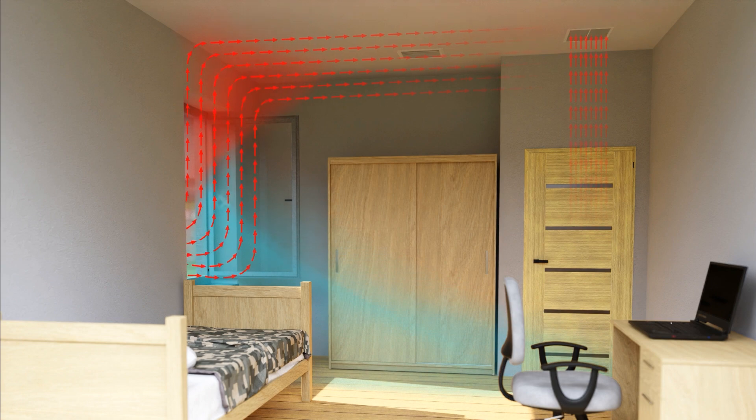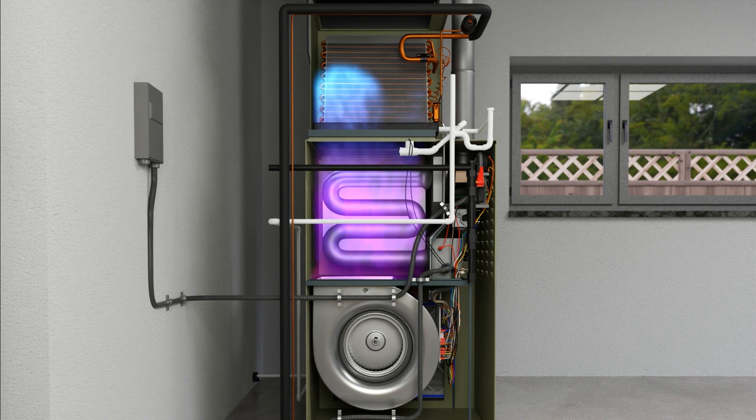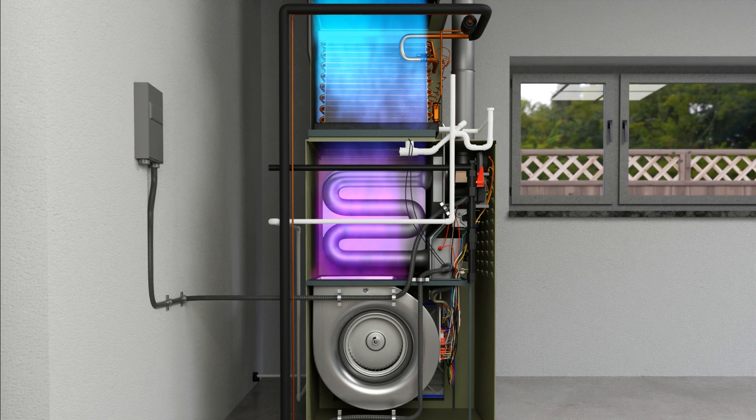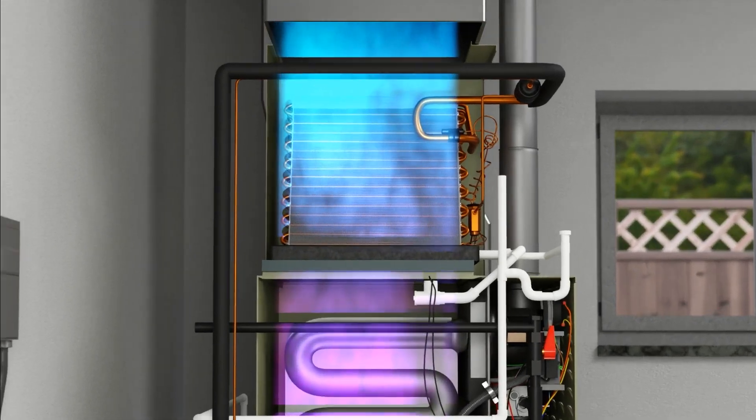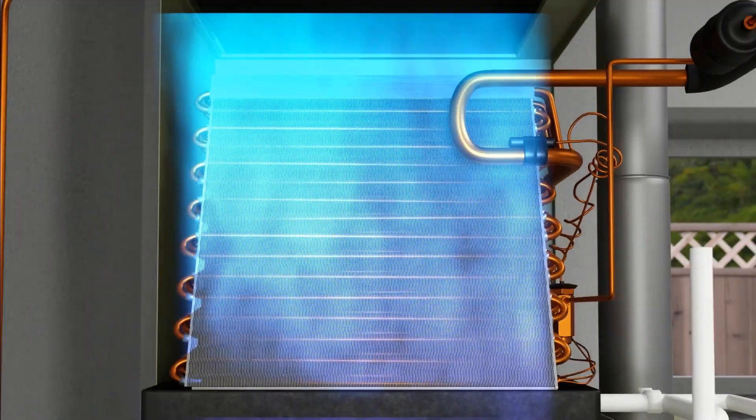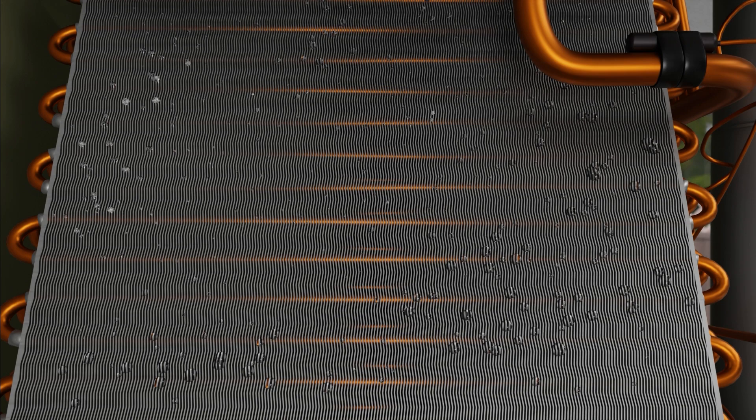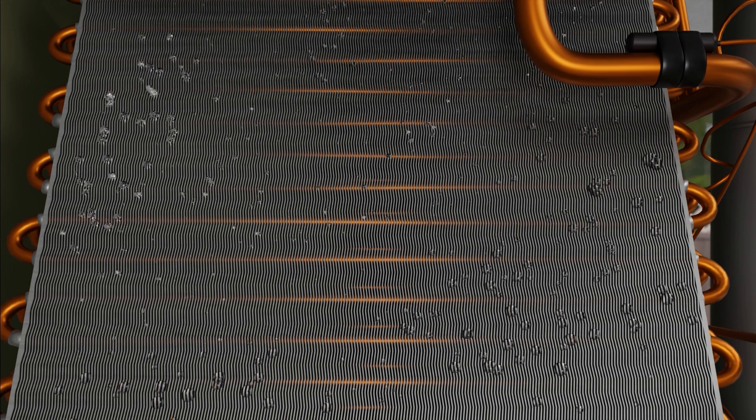You can see the air moving into the return of the HVAC system, which will take it into the unit here. When air passes over the evaporator coil during the cooling process, water condenses on the coil. Water vapor becomes a liquid. This type of transfer is called latent heat transfer because we can't measure the energy utilized with the thermometer, like we mentioned before.